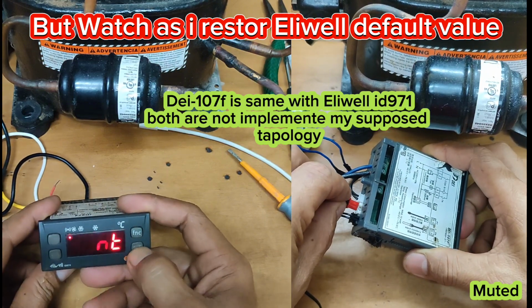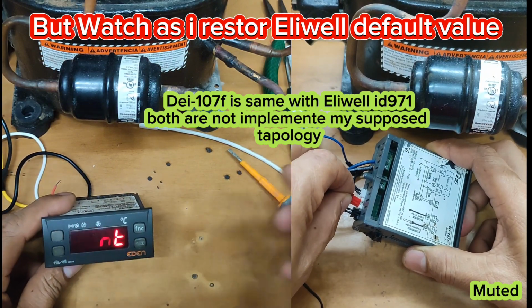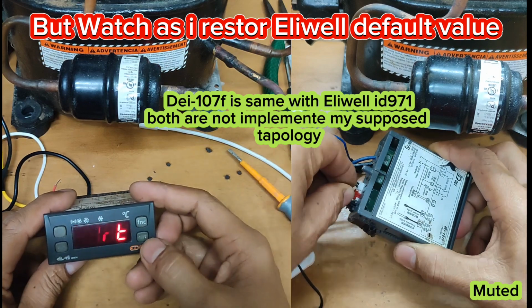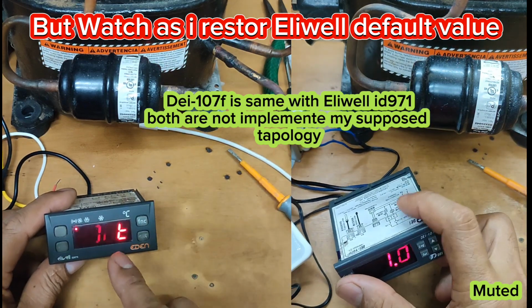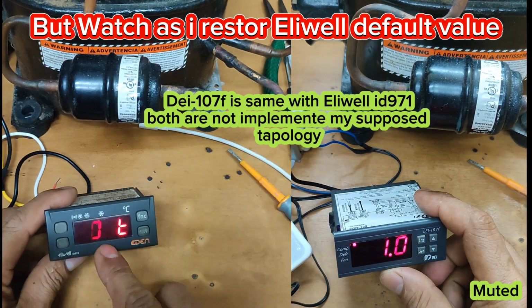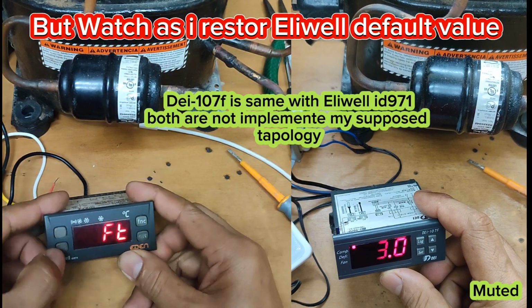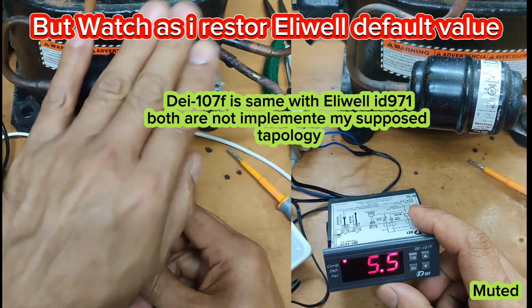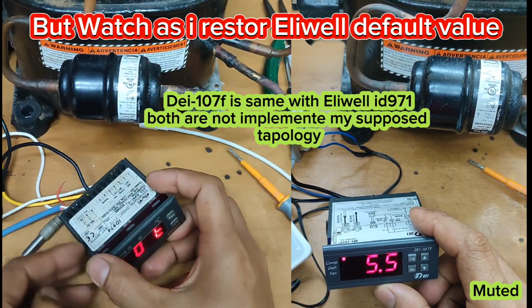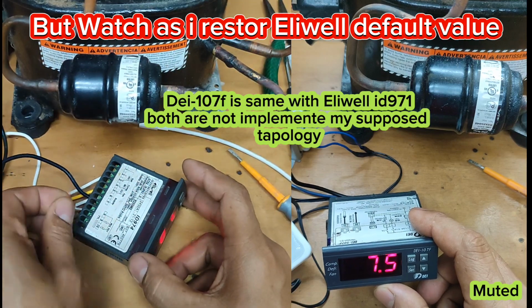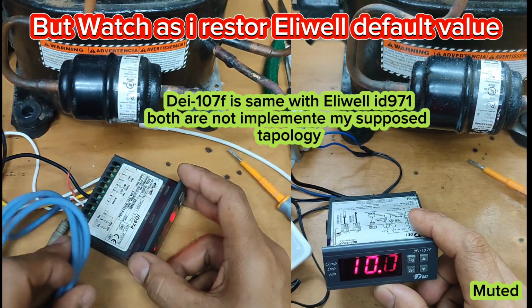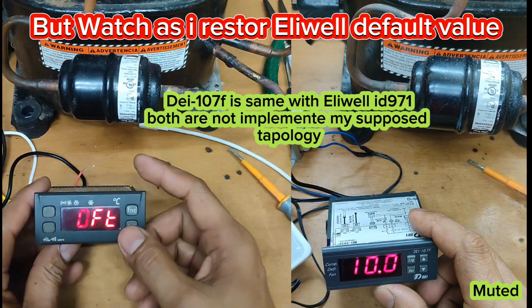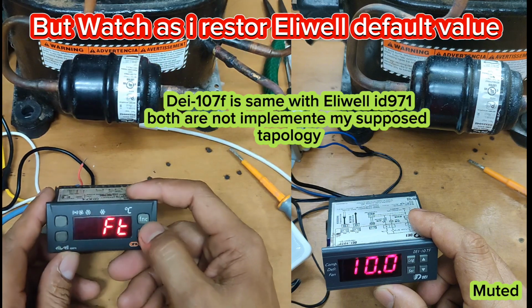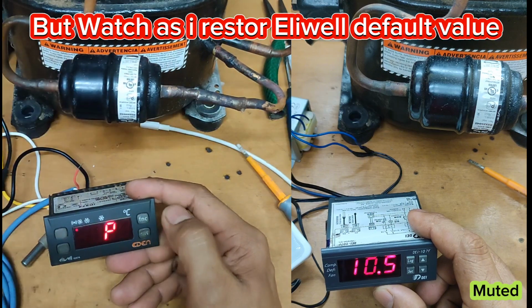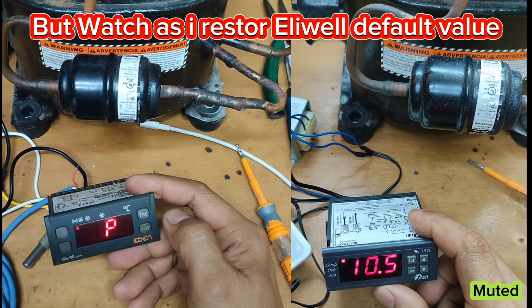If you download the manual of this one, you may find that once ONT is 0 and OFT is 1, this compressor is always off during a faulty probe. And I disengage this room sensor, and this is what happened. The compressor is off, and we're going to reset that.